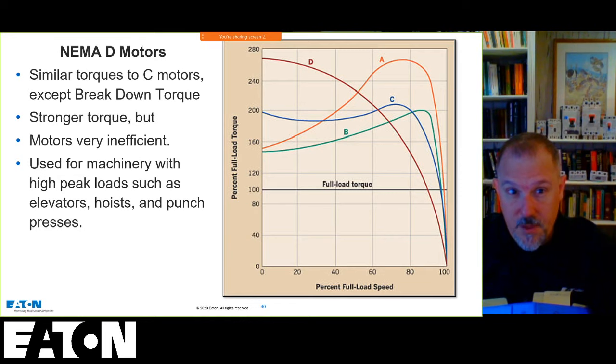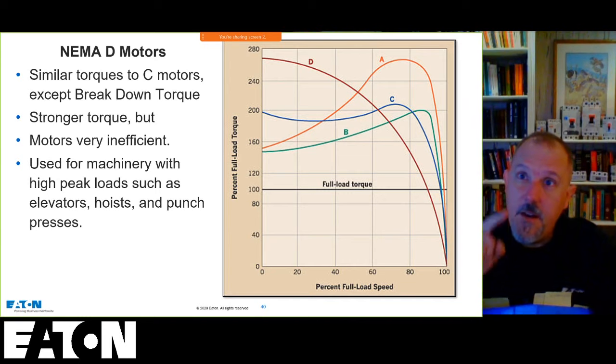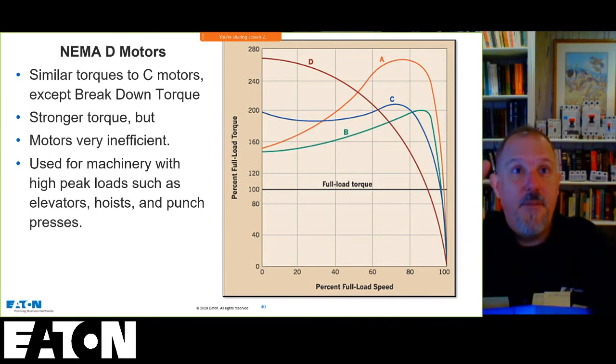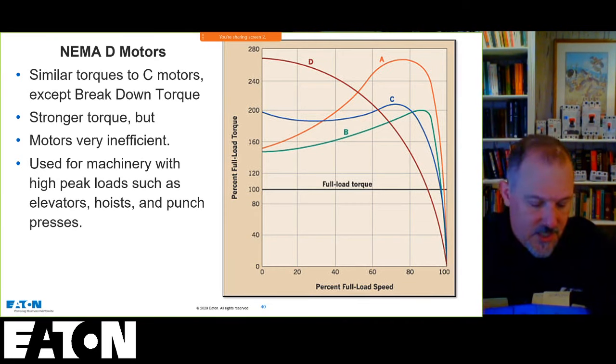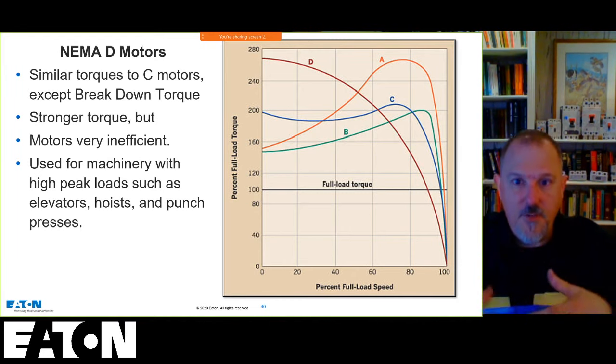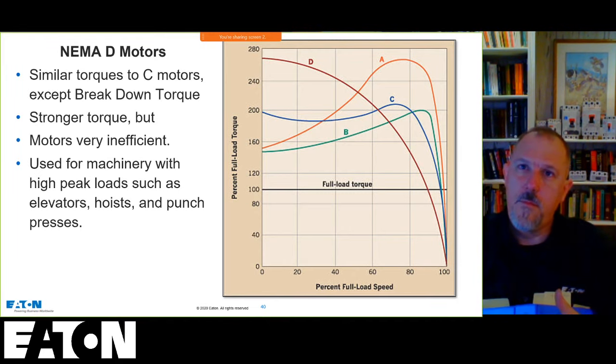And we know what happens with the speeds, right? We're usually changing frequency or voltage, something to change speeds. And then that will impact the full load amps. In which case, the nameplate current ratings shall be used. So very good point that was raised by Bob Fahey. Thank you. 430.6(A)(1) gives you those conditions. And again, the reasons are that...